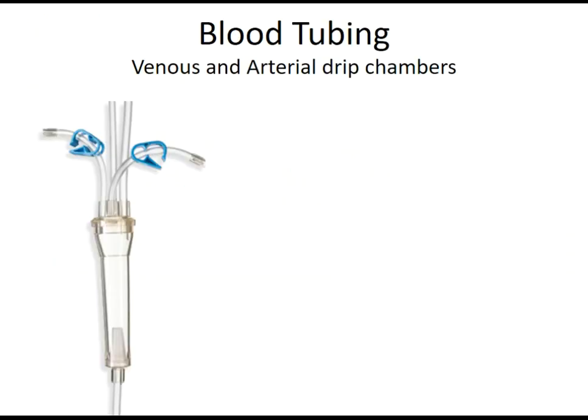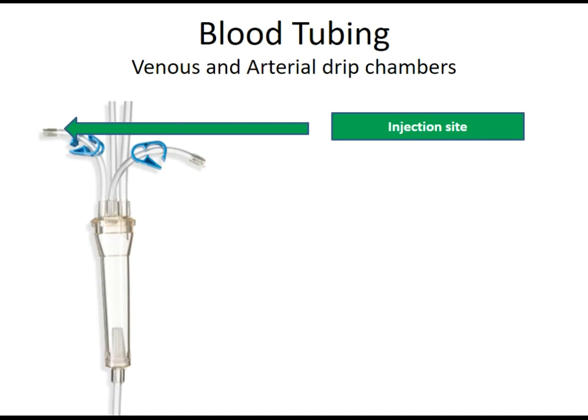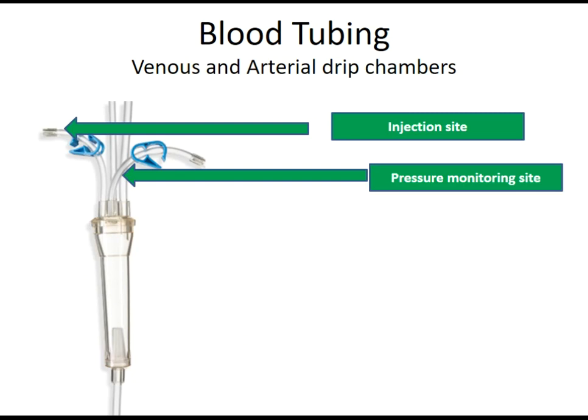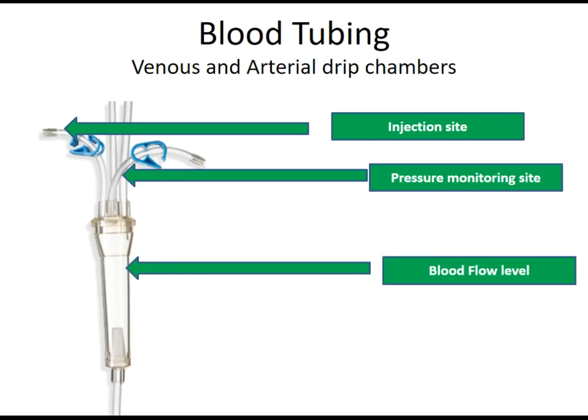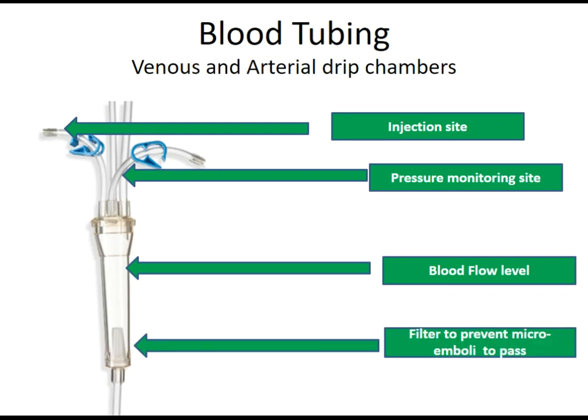The blood tubing has venous and arterial drip chambers. These include an injection site, a pressure monitor site attached to the transducer protector, a blood flow level indicator, and a filter to prevent micro-emboli from passing to the patient.